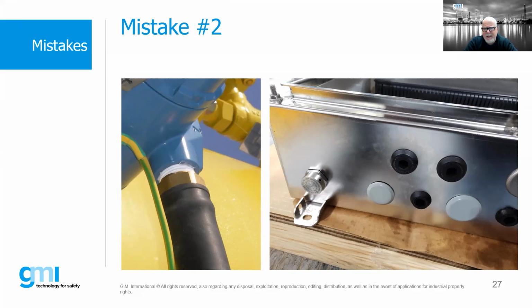And on the left-hand side, excuse me, that's where we see some Teflon tape. We do not want to put Teflon on any threaded entries, even though it's a great idea for plumbing fittings and water fittings. The fittings that we see here or cable glands, that's actually a flame path. And we don't want to impede the flame path, that metal to metal surface, by the use of Teflon tape. Thread lubricant is okay. Things like Teflon tape is not okay.